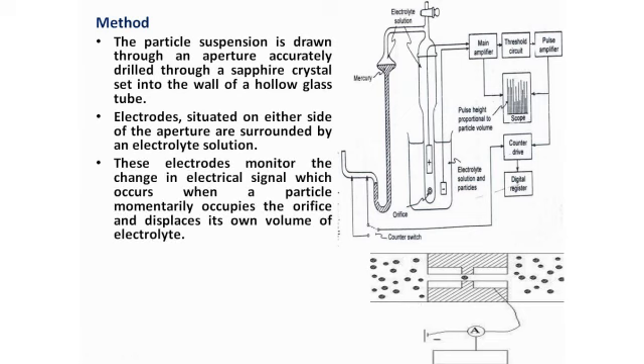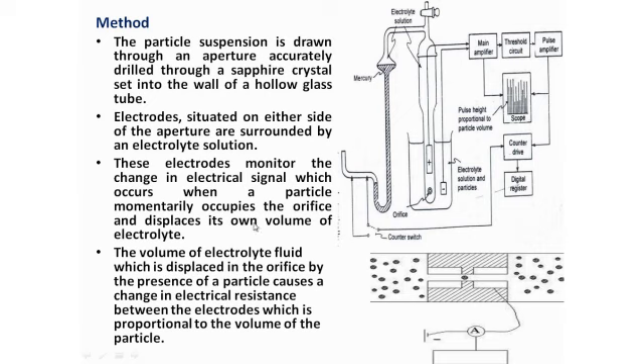The electrodes monitor the electrical signal which occurs when particles momentarily occupy the orifice and displace the electrolyte. When the particle momentarily displaces the electrolyte, it changes the electrical resistance. This signal goes through an amplifier and threshold circuit to count the particles.